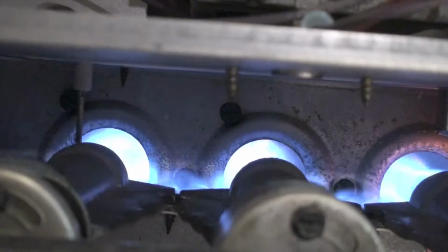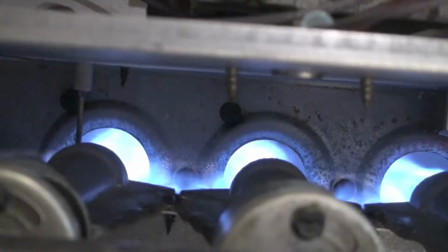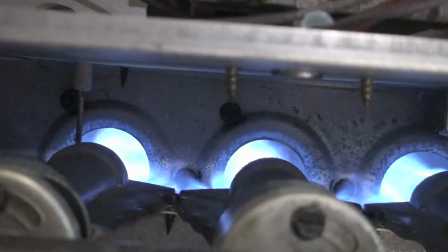The flame should go straight into the heat exchanger. Those little licking up flames between the burners are flame spreaders, and that's normal. There's nothing abnormal about it. But as soon as this blower comes on, you're going to see a change in the way the left 2 burners operate.